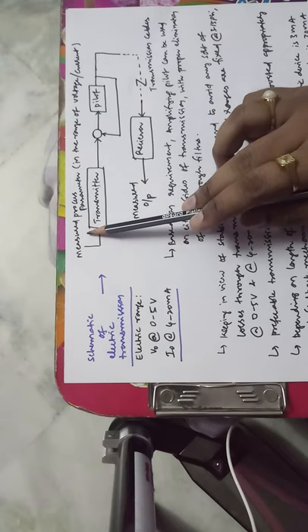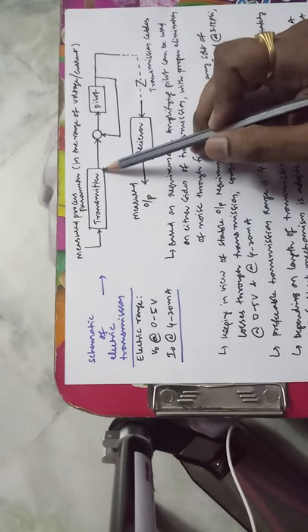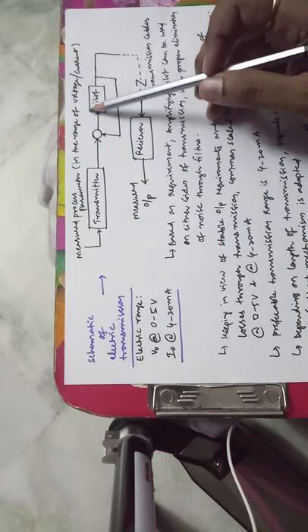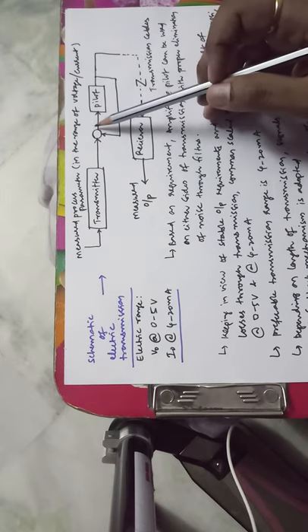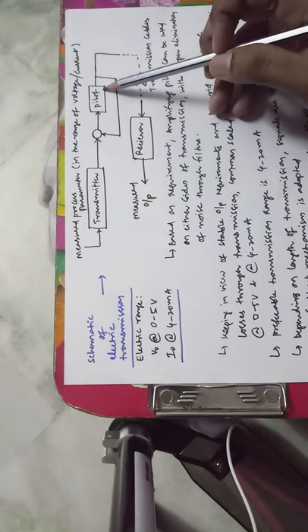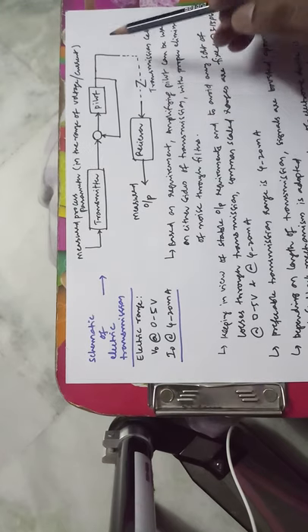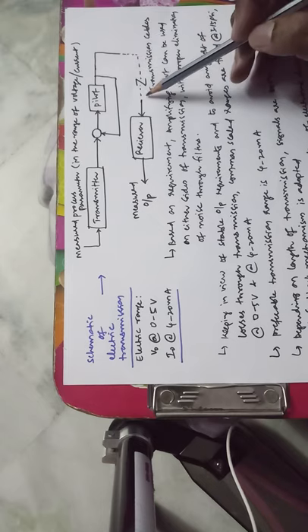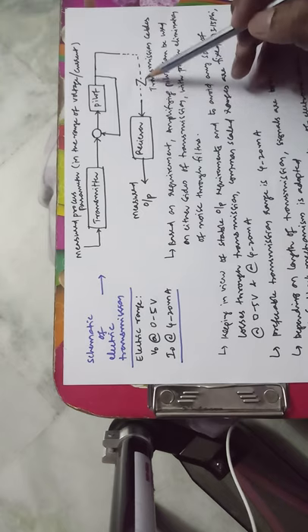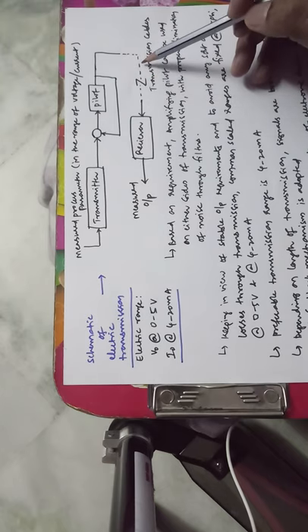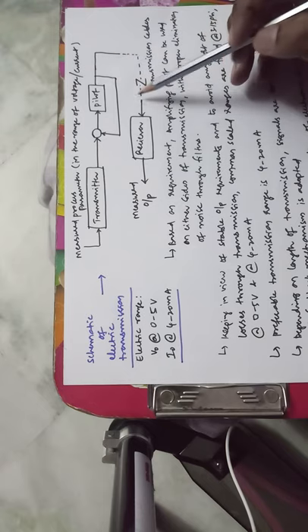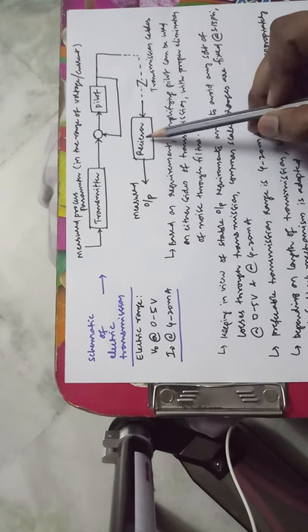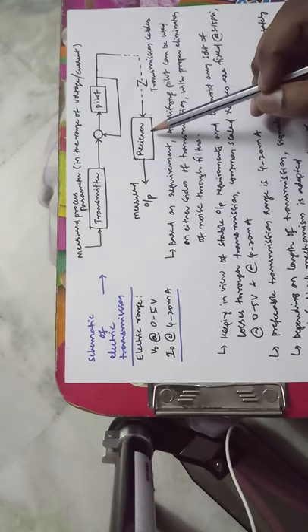The transmitter transmits the measured process parameter in terms of voltage, and this voltage is given to an amplifying pilot to boost the signal. Current is preferred over voltage to avoid the effect of cable resistance, since cable resistance can cause loss of voltage levels from transmitter to receiver. That is why current is preferred to avoid loss of the electrical signal.